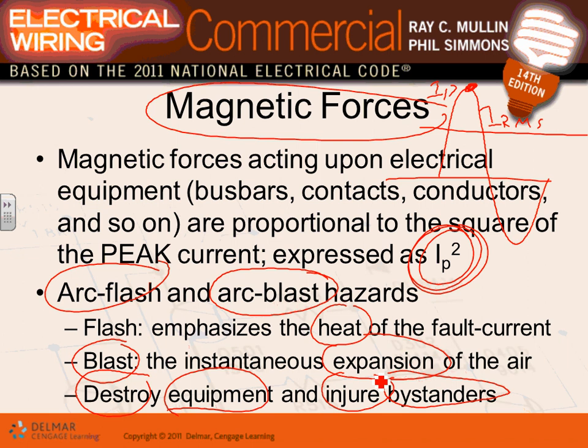If you don't put these labels there, it's a law, by the way. It is the law to have an arc flash label on the equipment with the energy that you're going to calculate. So the people working on energized electrical equipment know the danger that could happen from the arc flash and arc blast as a result of a ground fault or a short circuit condition. If you don't warn them, an average Joe apprentice would not know and might just go stick their fingers there, or drop the wrench there, and arc flashes. So that's a law.